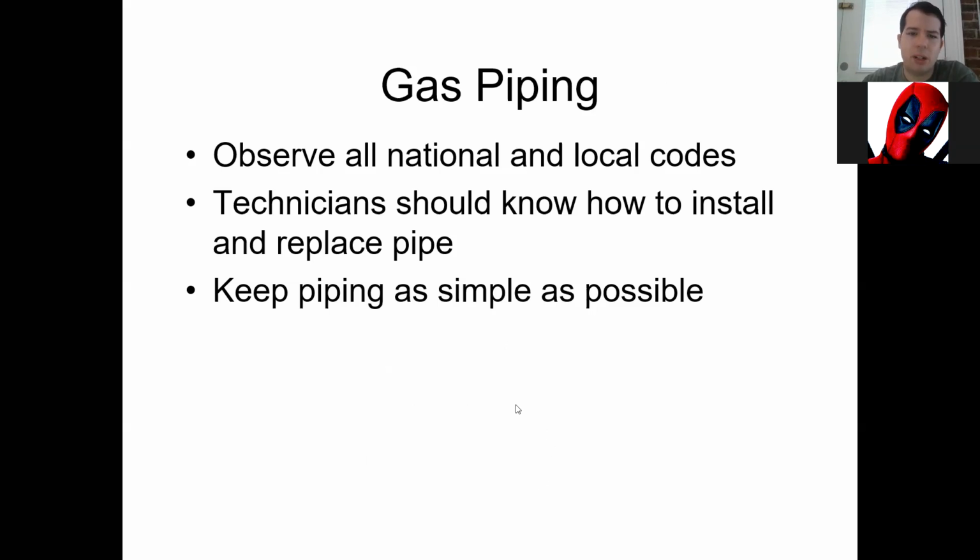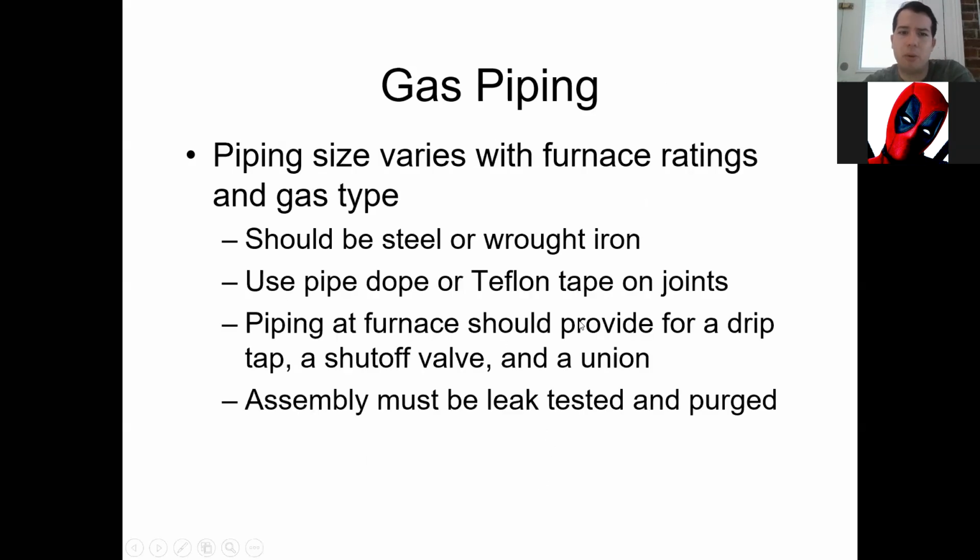We've got it where gas piping is going to be really important. So pipe dope is what I always recommend to use. Teflon tape is good for gas pipe connections, especially for propane, but pipe dope is usually a little more reliable, and it's easily seen visually, so a customer knows right away, okay, yes, I've got it, there it is, we're good. They can see it deteriorate, they can see it change color typically.